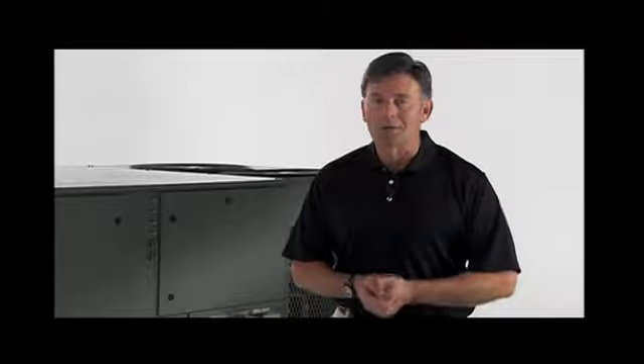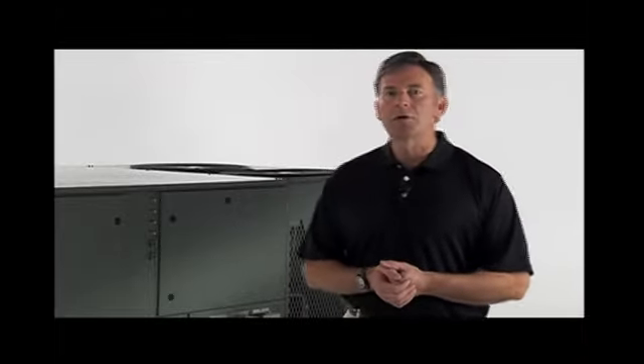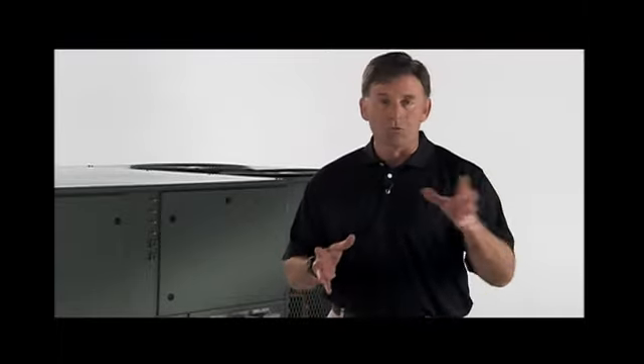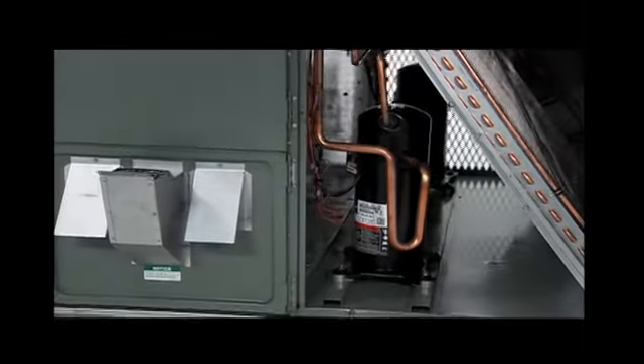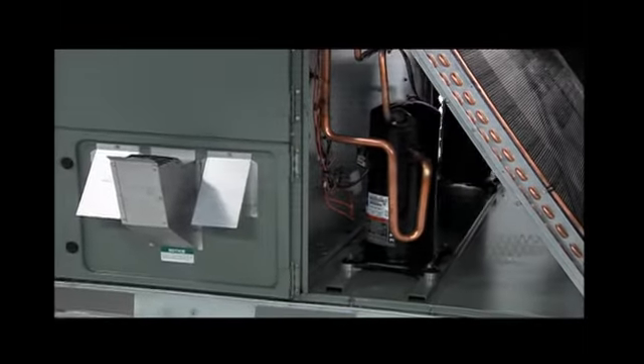Each furnace has the following safety devices to assure consistent and reliable operation. Pressure switches to assure adequate combustion airflow before ignition. Roll-out switches to assure no obstruction or cracks in the heat exchanger. A limit device that protects the furnace from over-temperature problems. For heat pumps and cooling-only units, the electric heater kit inserts in the area where the gas heat section is located in this unit. The compressor compartment houses the heartbeat of the unit.